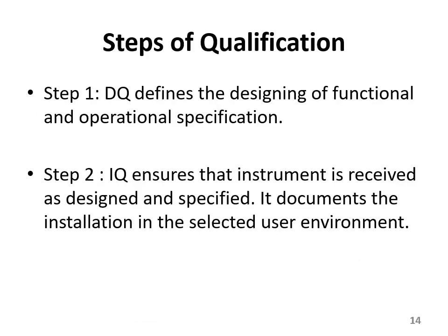Okay, steps or the phases of qualification. Step 1, design qualification, DQ. This defines the functional and operational specification of a balance, instrument, or a process, right?